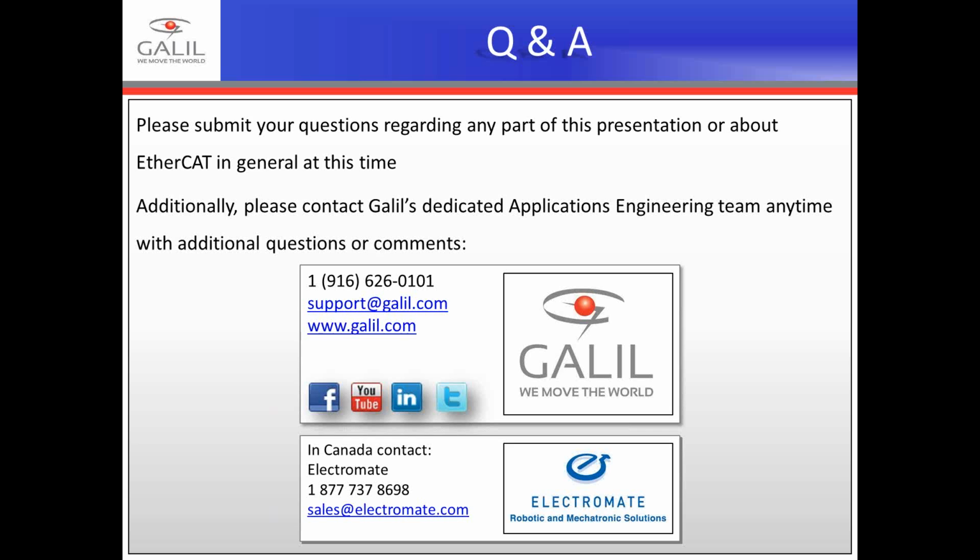Our next question is, my application uses a combination of electrical and hydraulic servos, as well as 2 low-power stepper axes. How is this addressed by EtherCAT connectivity? Since the EtherCAT standard essentially defines where that profile data is written to, the type of motor or actuator is transparent to the master. You tell either the servo to move to a position, the stepper to move to a position, or the actuator to move to a position.